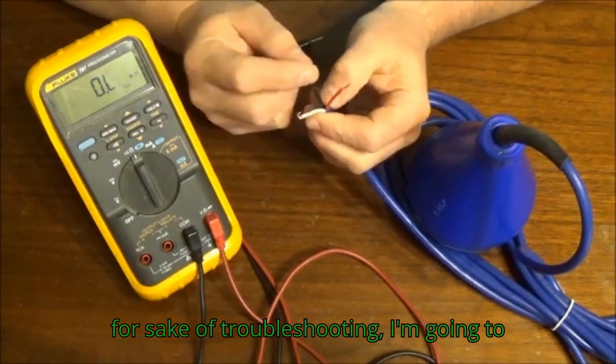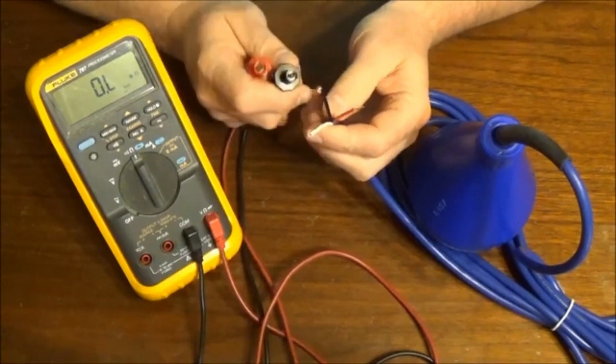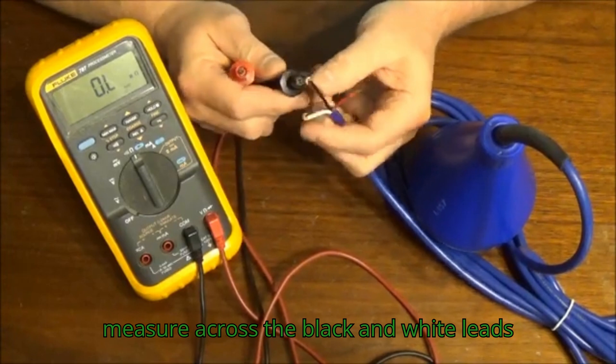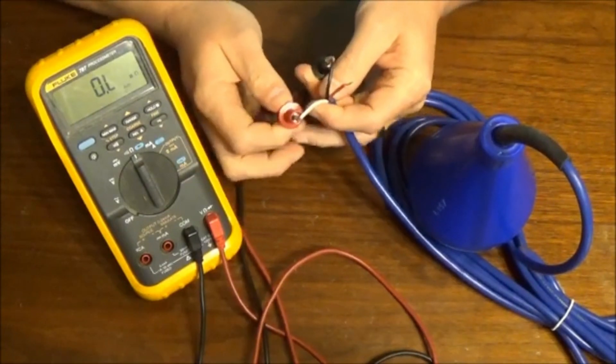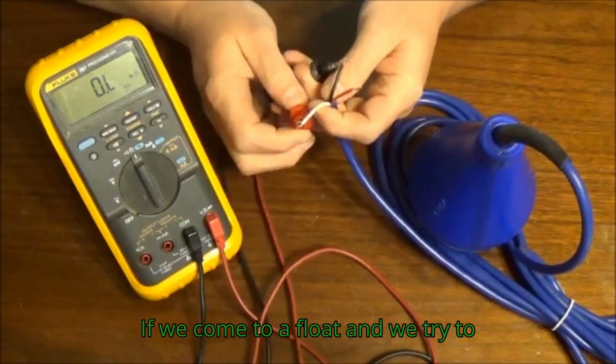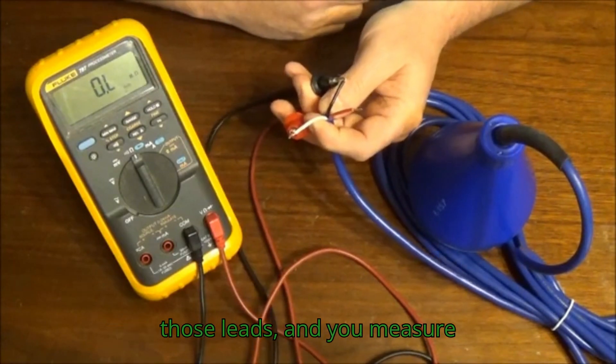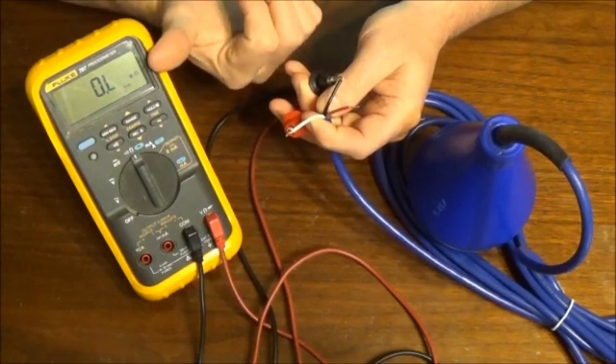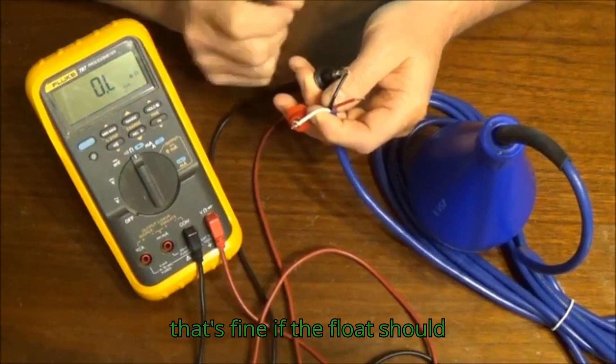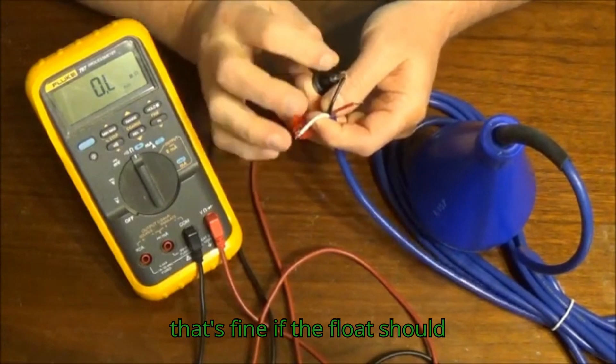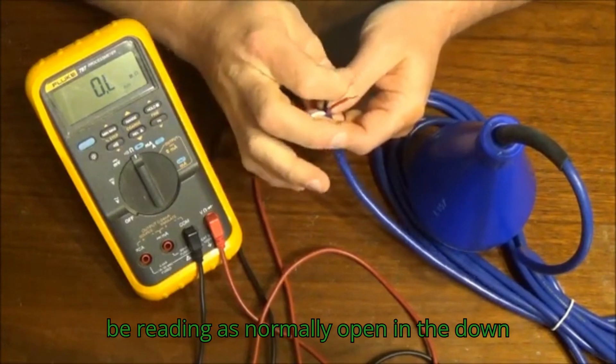For sake of troubleshooting, I'm going to measure across the black and white leads, implying that if you come to a float and try to troubleshoot it, and you measure across those leads and you measure OL, that's fine if the float should be reading as normally open in the down position.